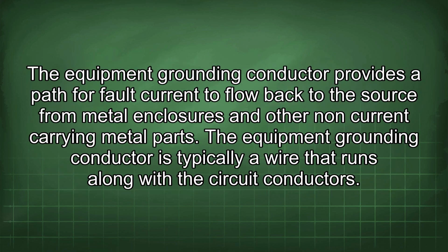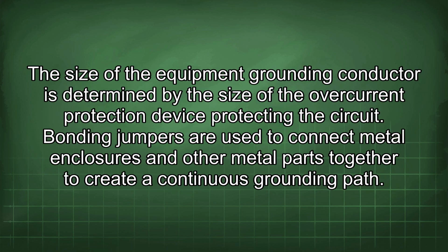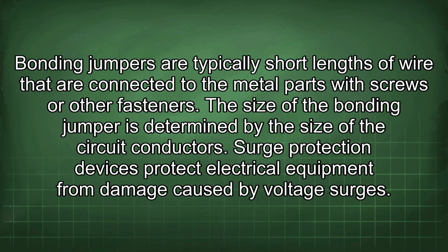The equipment grounding conductor provides a path for fault current to flow back to the source from metal enclosures and other non-current carrying metal parts. The equipment grounding conductor is typically a wire that runs along with the circuit conductors. The size of the equipment grounding conductor is determined by the size of the overcurrent protection device protecting the circuit. Bonding jumpers are used to connect metal enclosures and other metal parts together to create a continuous grounding path. Bonding jumpers are typically short lengths of wire that are connected to the metal parts with screws or other fasteners. The size of the bonding jumper is determined by the size of the circuit conductors.